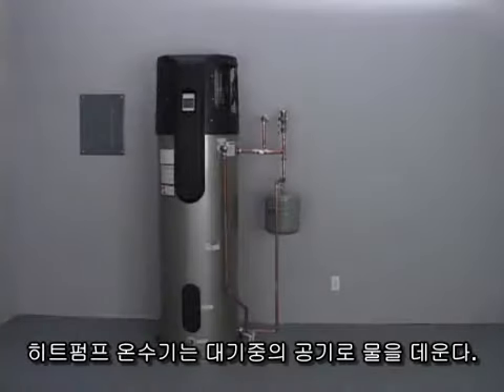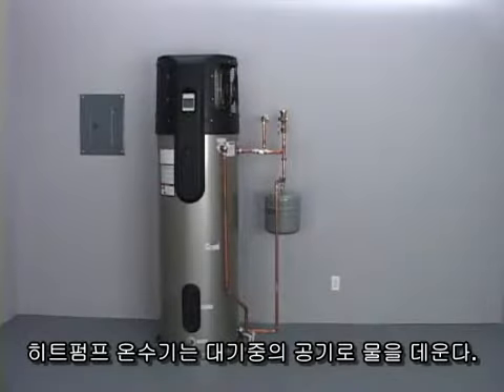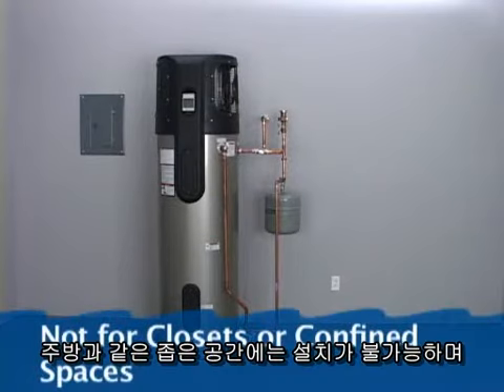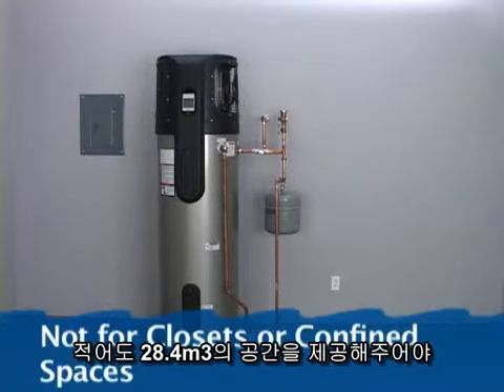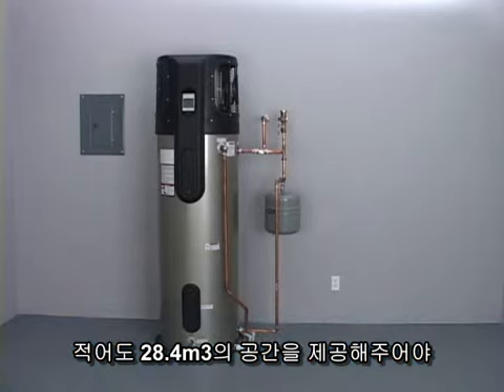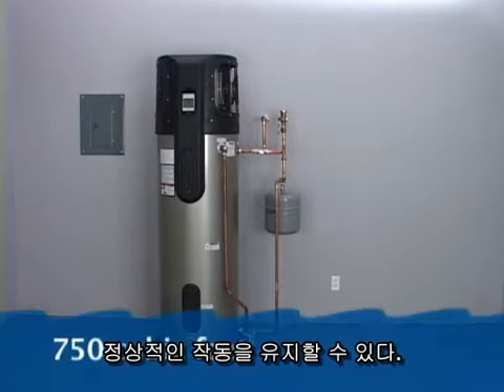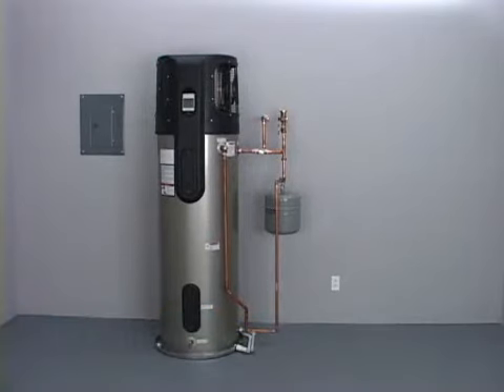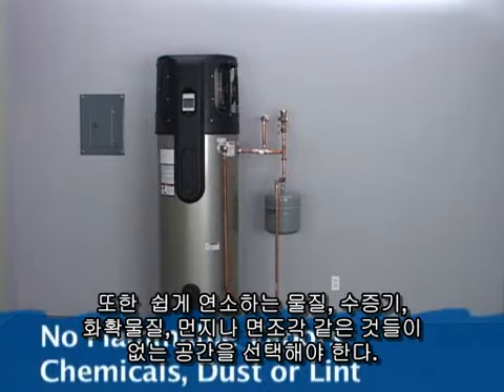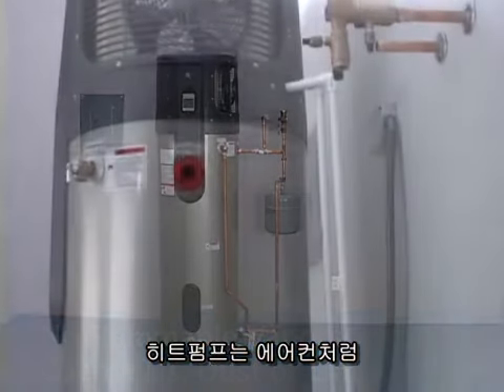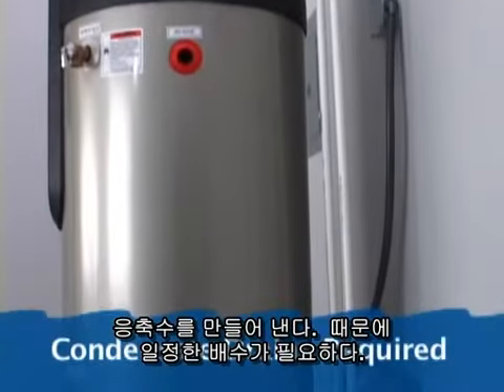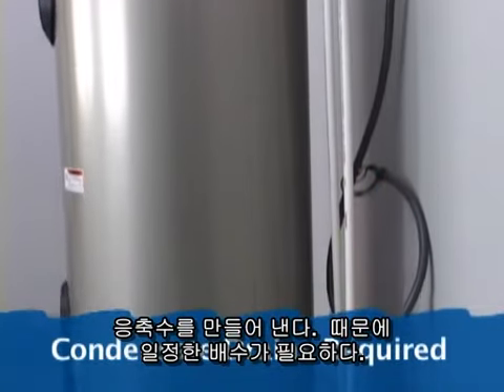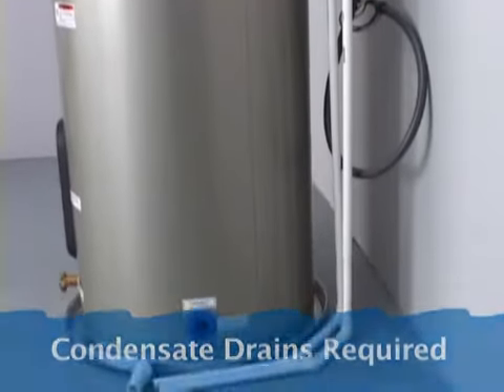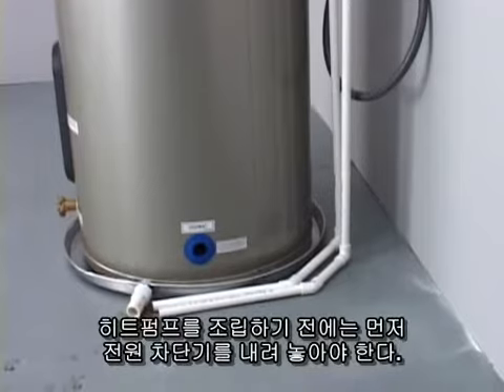Heat pump water heaters efficiently use room air to heat water and must not be installed in a closet or other confined space. A room size of at least 750 cubic feet is recommended for efficient operation. The room air should be free of flammable vapors, chemicals, dust, or lint. Heat pump water heaters also produce condensation, just like an air conditioner, and this condensation must be drained properly.